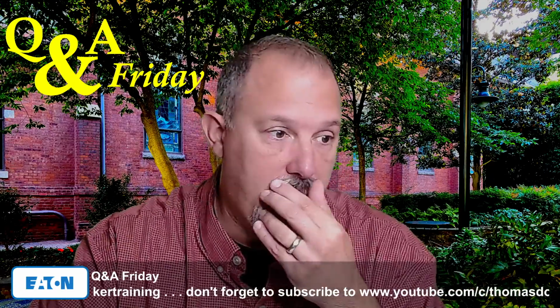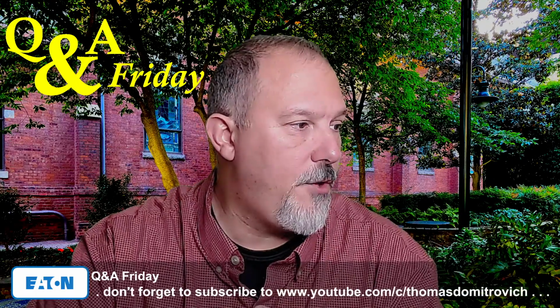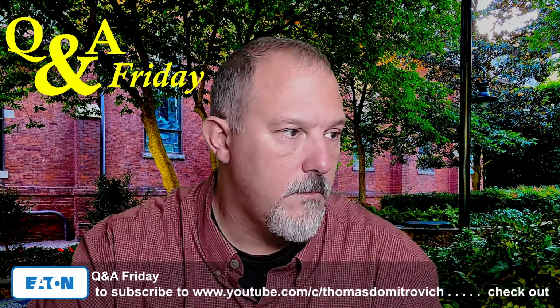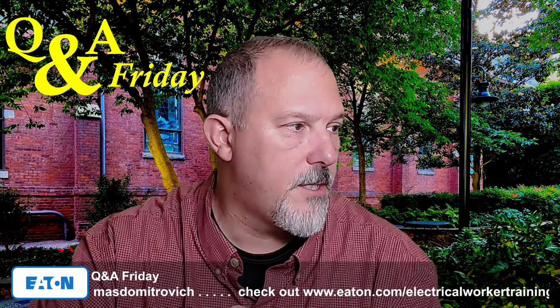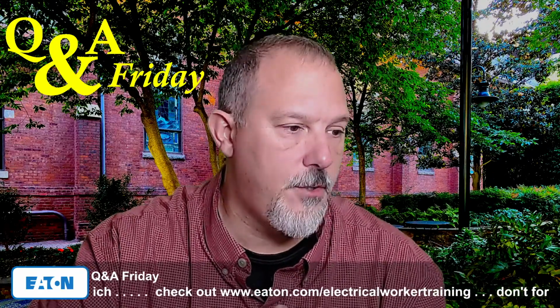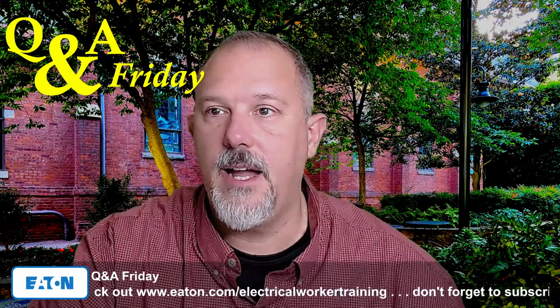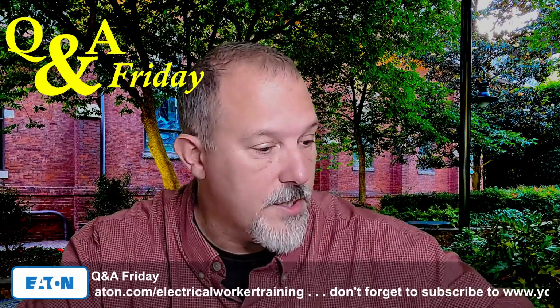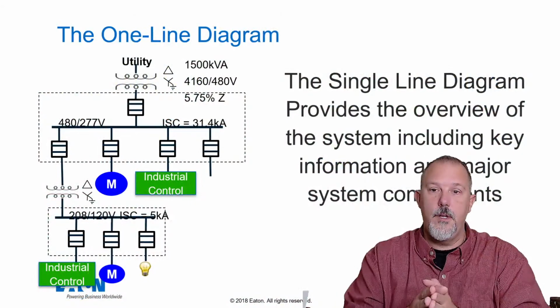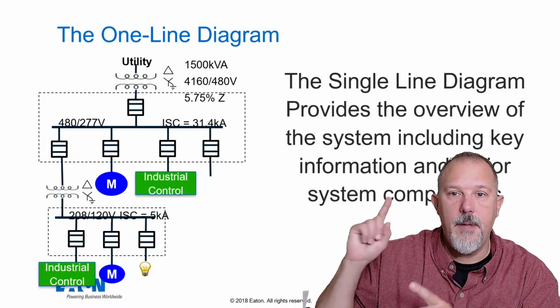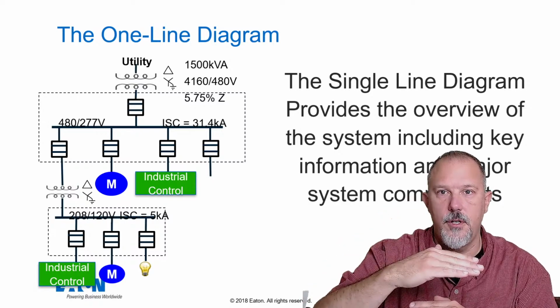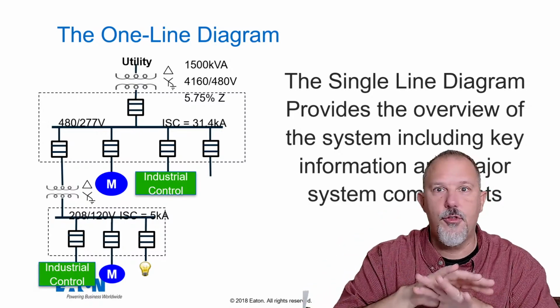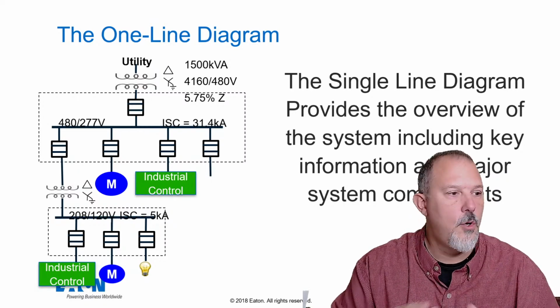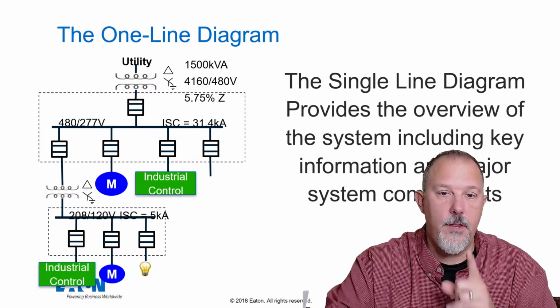I got to talk to you about this one too, because of what you just said. Let me do this. I'm trying to find a decent one-line diagram, because here's the other issue I've run into: in some cases I've had individuals say that all they do is put a main overcurrent device, which is a fuse, which will reduce the fault current, RMS, throughout the entire power distribution system, which is not right.